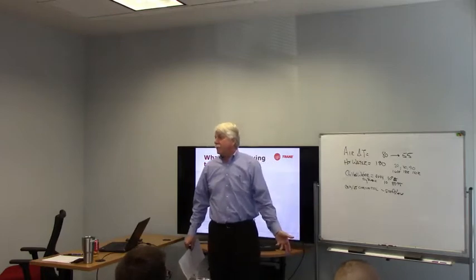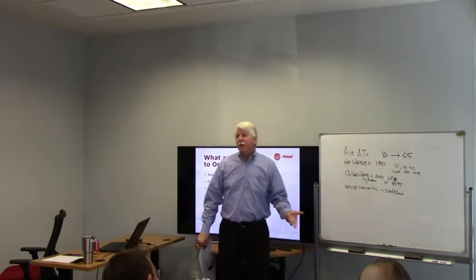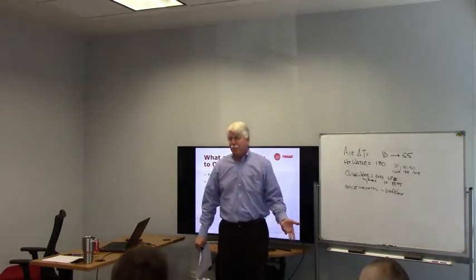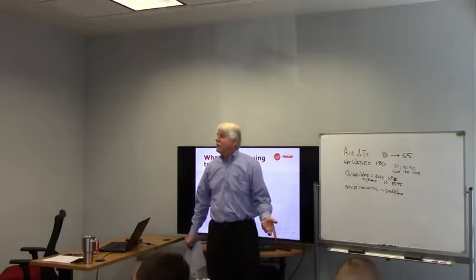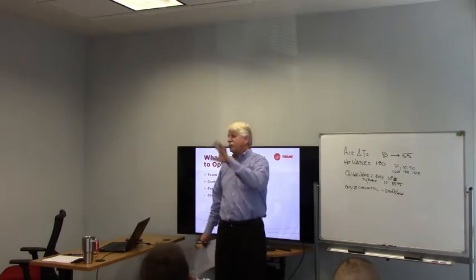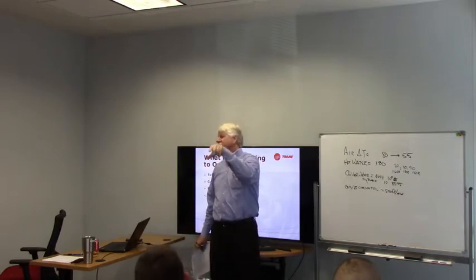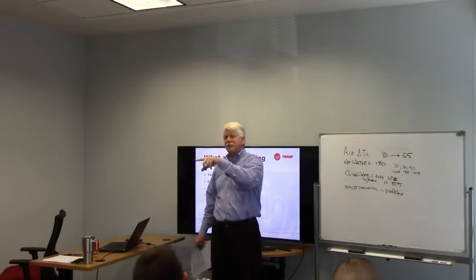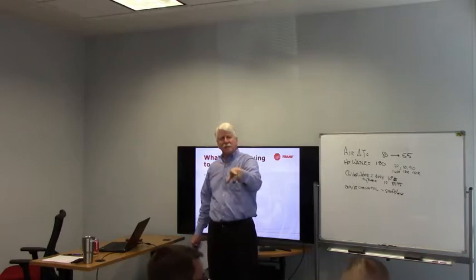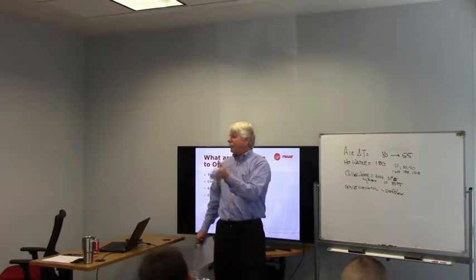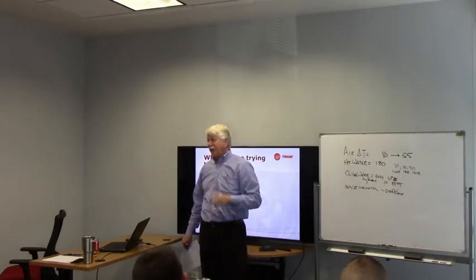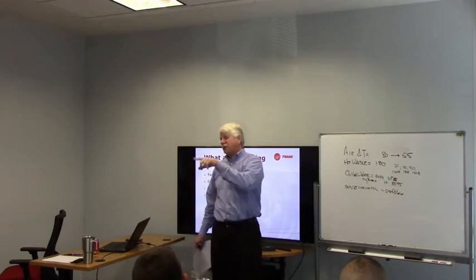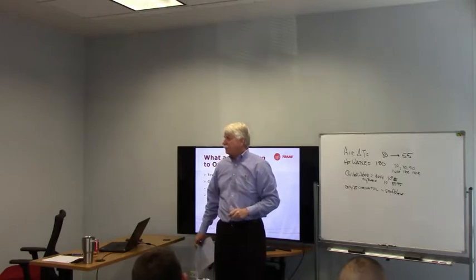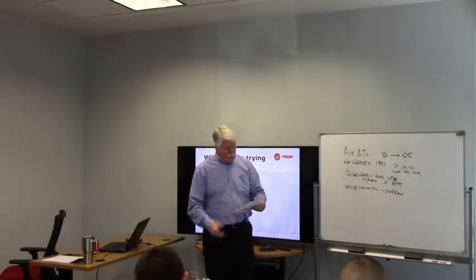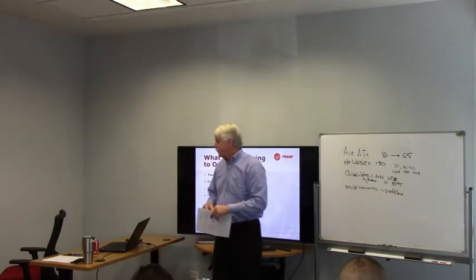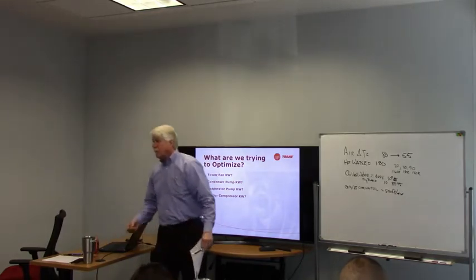Okay? On other Trane equipment, do you know how to tell on a Voyager what the tonnage is? Wait, can you say that again? How can you tell square feet of a Trane air handler again? Model number. Which number? It's usually 4 letters, like MCCA was the old model, modular climate changers. Now they're CC something, CSAA, 4 letters, something like that. But after the 4 letters, there'll be 3 numbers. And if it's like 012, that means it's 12 square feet. If it's 063, it means it's 63 square feet. Okay? You know how to tell the tonnage of a Voyager rooftop? It's a model number 2, isn't it? Okay? What does the model number say?